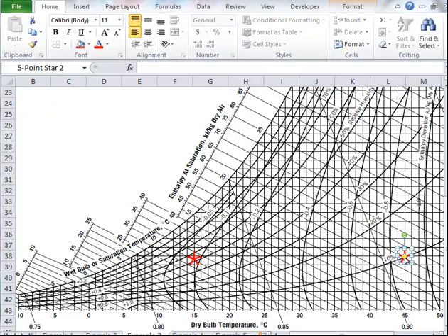If I cool it at constant pressure, then it's going to stay right on this constant humidity line. In other words, the amount of air and water in the curve will not vary. And so it comes over to this point, right over here on the same humidity line, until it's at 15 degrees C. Now at this point, I'm going to stop the problem. It has not reached the saturation curve, this top edge, so therefore nothing will condense.